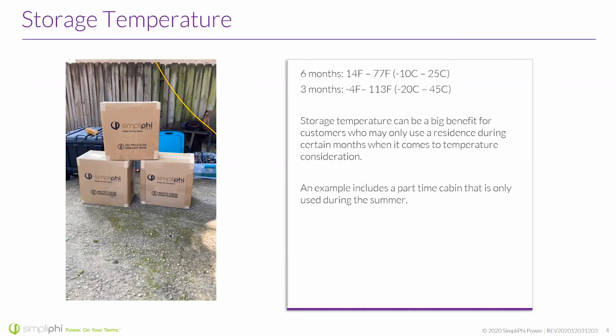The storage temperatures, 6 months. That meaning if you're going to store the batteries for 6 months, 14 degrees Fahrenheit to 77 degrees Fahrenheit. So -10 degrees Celsius to 25 degrees Celsius. 3 months, -4 degrees Fahrenheit to 113 degrees Fahrenheit. So -20 C to 45 C. So as you can see there, it relates more to cold temperatures than hot temperatures. So again, this is a great way to save the batteries and use them in applications where maybe you are only using the system in the warmest months and storing the system in the cold months, even in that cold location.